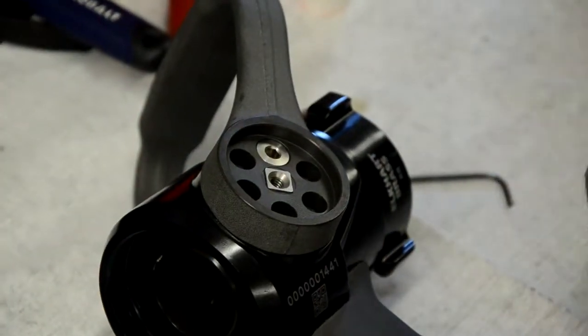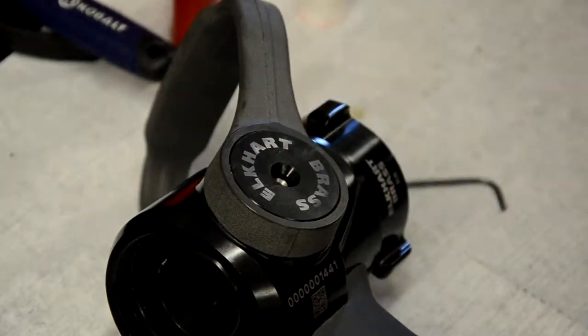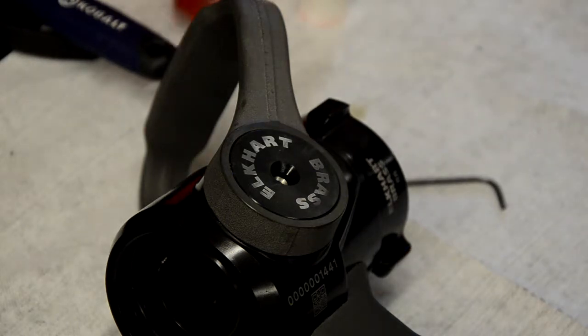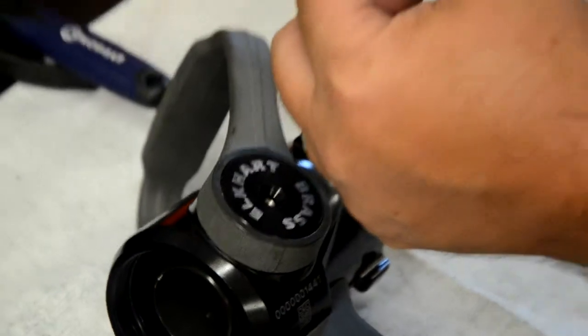Next, put a small amount of Dow Corning number 7 silicone grease inside the bail handle recess where the actuator shaft cover o-ring will contact. Position the bail handle in the open position, align the word Elkhart so that it reads upright, and press the cover into place until it stops.